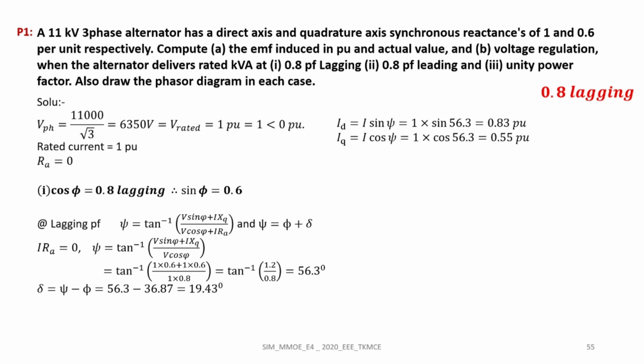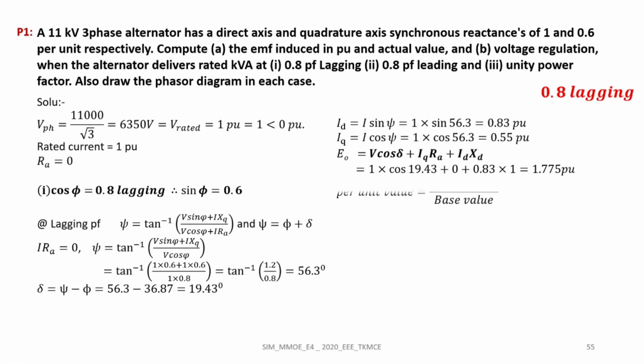Then we know the expression for E0 as V cos delta plus Iq Ra plus Id Xd. Substituting different values in this equation, we can obtain E0 as 1.775 per unit. We know per unit value is equal to actual value by base value. So we can obtain the actual value as per unit value into base value. Here this is the induced voltage in per unit that we need to convert into line value and phase value, actual values. So we multiply this per unit value with the base value in kV, and we can obtain the actual value of induced EMF in line value.